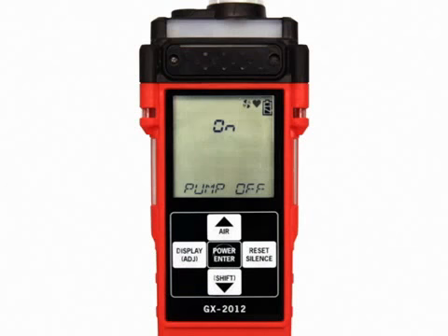This item appears in display mode only if Pump Off display is turned on in maintenance mode. A GX2012 pump can be turned on and off in this screen. This feature can be used to conserve battery life if there is a significant period of time until the next gas monitoring task, but you do not want to wait for the warm-up sequence to complete if you turn the instrument off and on again.